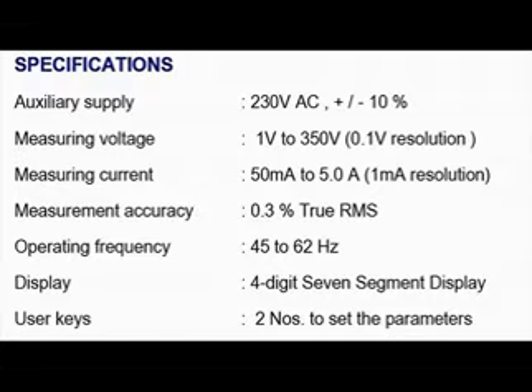You can see on the screen, the auxiliary supply voltage is 230 volt AC plus minus 10%, but the auxiliary supply can be anywhere from 5 volt. You only need a power supply that brings down the voltage to 5 volts for the circuit to work. So an auxiliary supply need not be 230 volts in all applications. The measuring voltage as of now on our board that we are going to demo is from 1 volt to 300 volts, but by changing a couple of resistors we can go to any other voltage range needed.